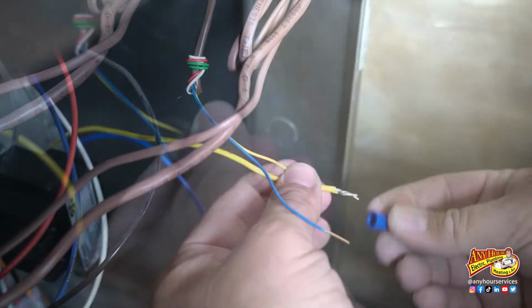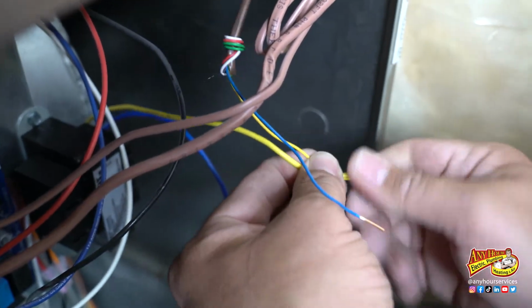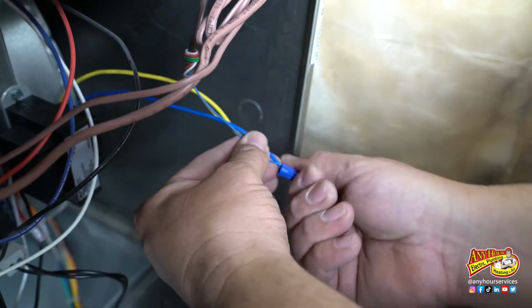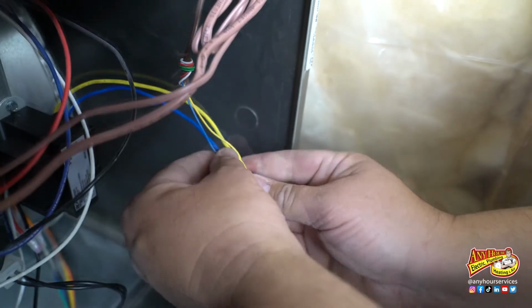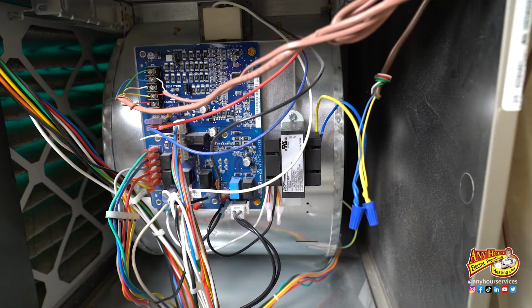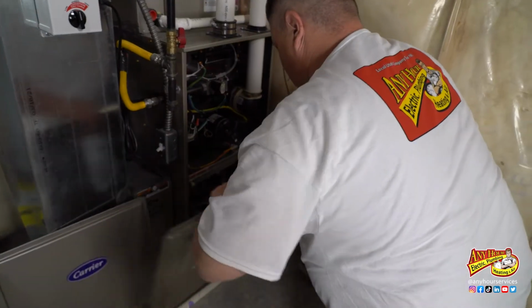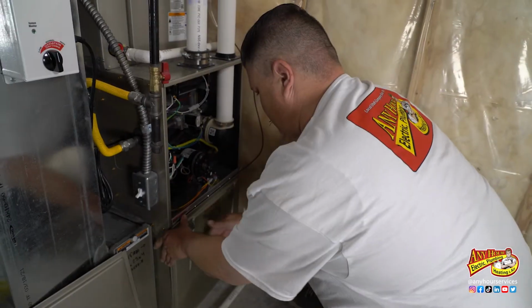Since I used thermostat wire, I'm going to use the yellow and the blue conductor to keep things consistent with the color of the wires coming off the low voltage side of the transformer. Strip the conductors and wire nut them to the corresponding colors. We should be done inside the furnace cabinet, so go ahead and button that up.